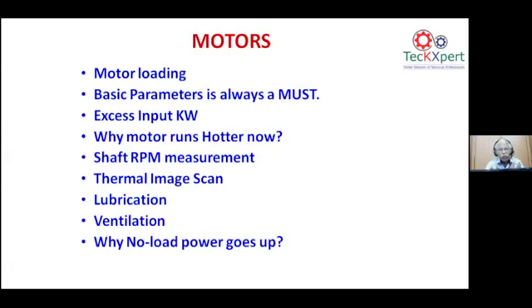Where we stand around 60 to 80% is the efficient loading, we all know. But still, the basic parameters like the voltage and current for the given motor are definitely worth monitoring, to see whether there is current unbalance or voltage unbalance. All the inputs, I'll come to in the next few slides, where we are missing and why this breakdown comes in a given motor due to not fixing the problem with the existing parameters.